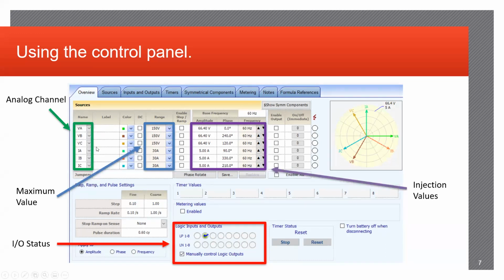So here on the left in the green square is your analog channel names. Again, this is what you'll be utilizing to identify which phase and which current or voltage source you're going to be using. This blue square here identifies the maximum range that you're going to be outputting. This is usually just a safety measure in case you accidentally mistype a value that you're going to be injecting. If it's too much and the relay can't handle it, you could burn up the contact, or even worse, just shut off the relay completely and trash it. So setting these current and voltage ranges is important for safety measures, as well as ensuring that the equipment is going to be safe if an error were to occur.